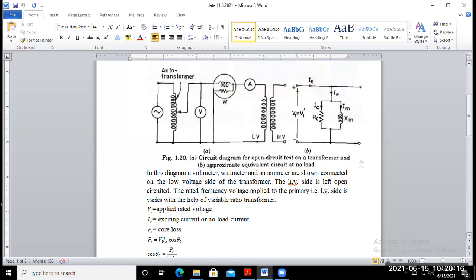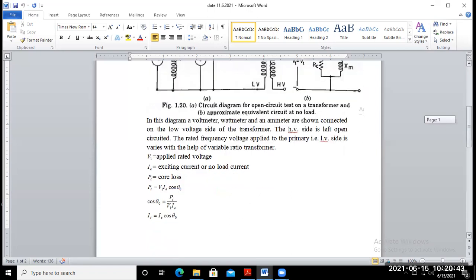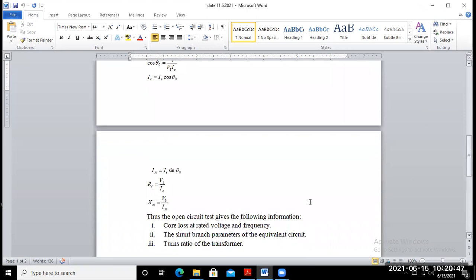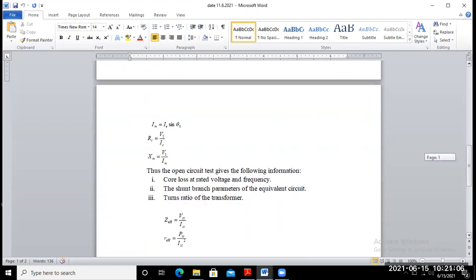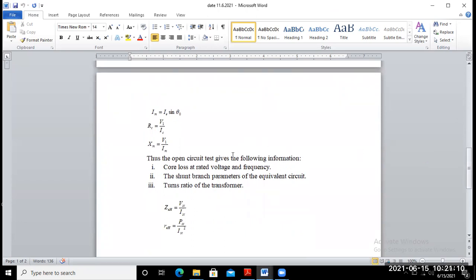So with the help of open circuit, no load test, we can find out the no load losses or core losses. And in parameters, you can find the core loss resistance, that means RC and XM. You must remember these tests are performed at the rated voltage, at the low voltage side, with HV kept open. So the open circuit test gives the core loss at rated voltage and frequency, the shunt branch parameters of the equivalent circuit, that means RC and XM, and the turns ratio of the transformer if one voltmeter is also connected on the HV side.